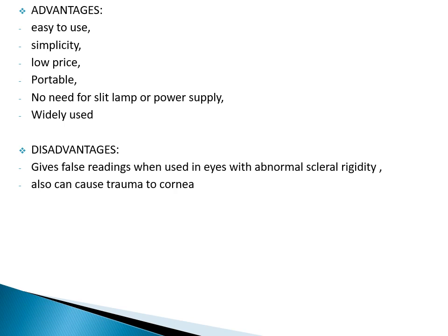Advantages of Schiotz: it is easy to use, it is a simple technique, having low price, it is portable, there is no need for a slit lamp or power supply, and it is widely used. Disadvantages are: it can give false readings when used in eyes with abnormal scleral rigidity. It can also cause trauma to the cornea.